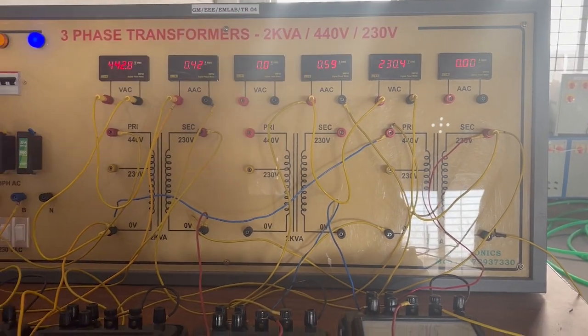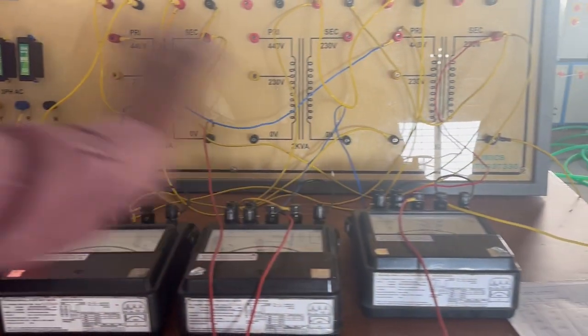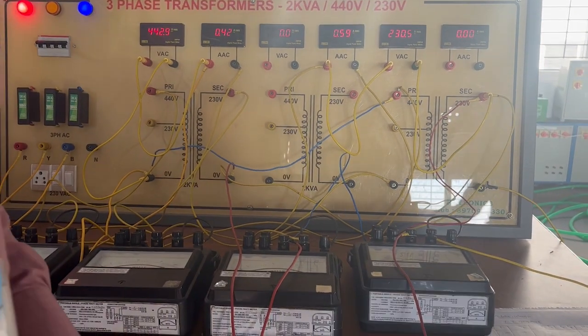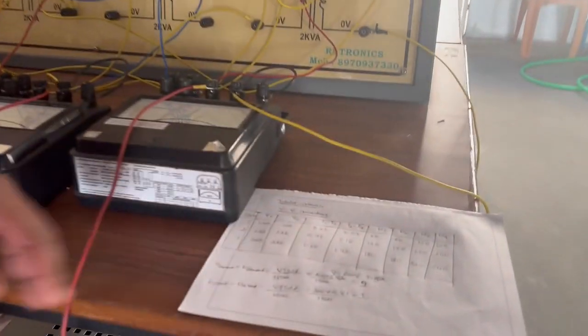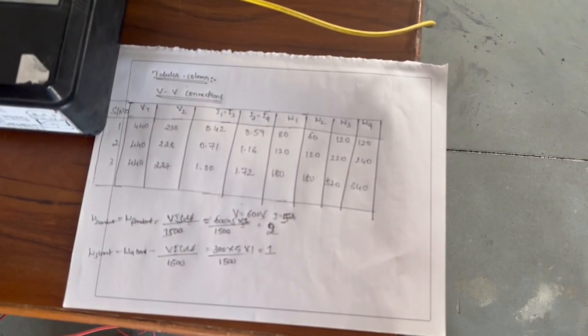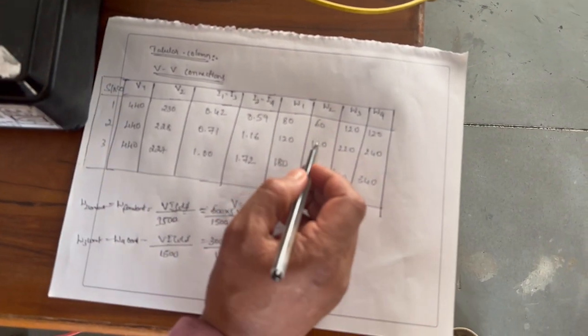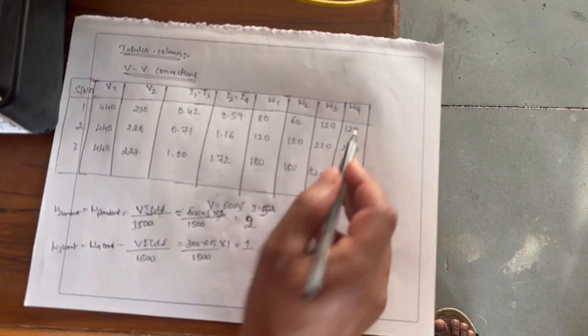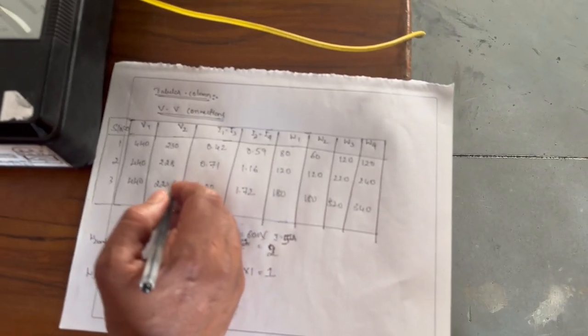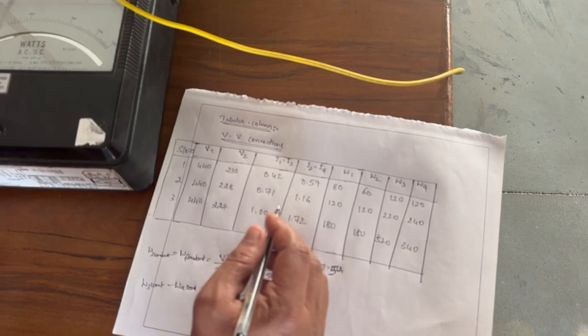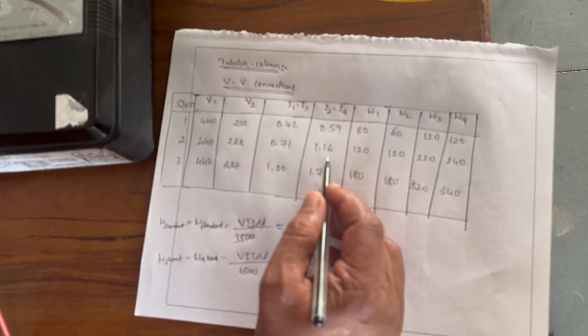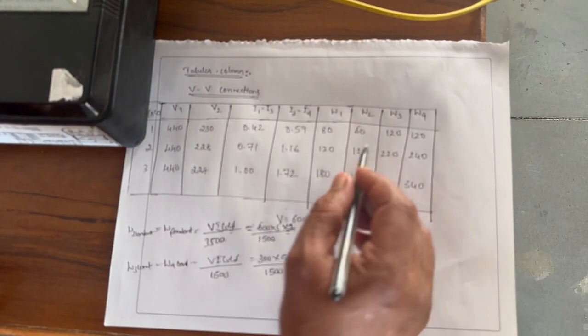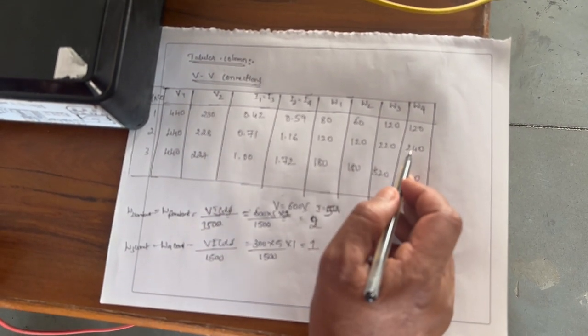This is V1 and this is V2. This is I1 and this is I2. Now this is W1, W2, W3 and W4. Now we have to take the readings. V1 is 440 volts, V2 is 230 volts and the current is 0.42. Next, W1 is 80, W2 is 60, W3 is 120 and W4 is 120. Next we take one more reading. Now V1 is 440, V2 is 228, I1 is 0.71 and I2 is 1.16. W1 is 120, W2 is 120, W3 is 220 and W4 is 240.